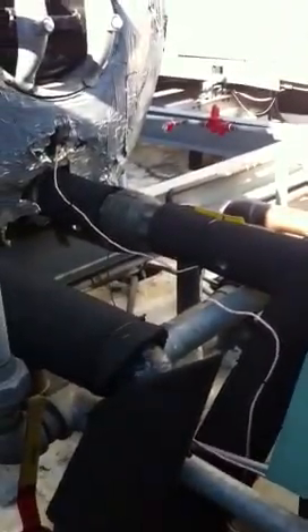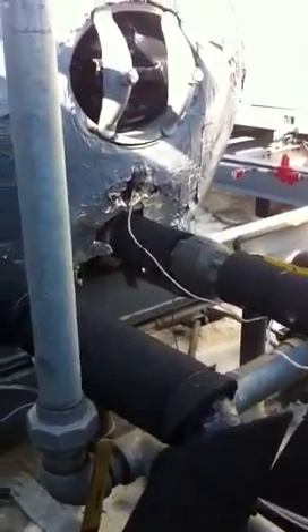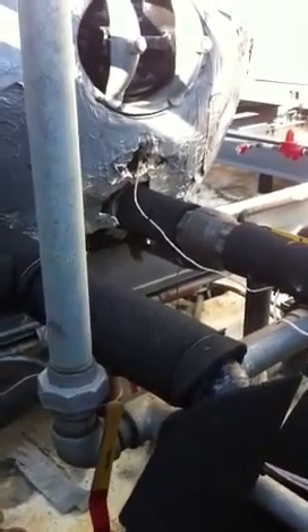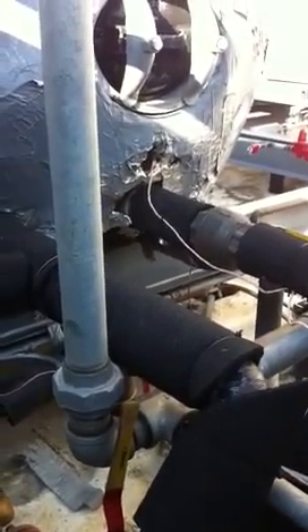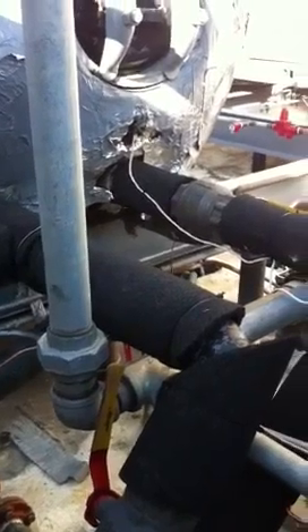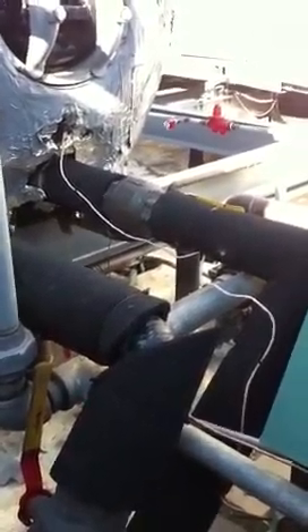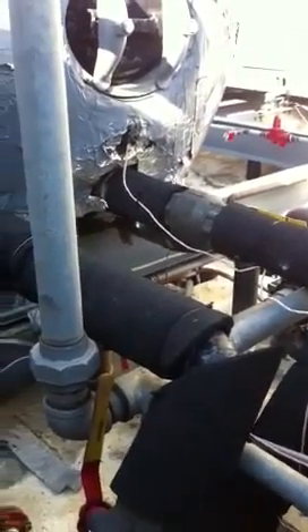It's just you're pumping through a lot more stuff that you don't have to. Plus, when the burner isn't on, the boilers act as radiators. So if you're pumping hot water through there, you're losing heat out of your hot water. So we also said that we're going to do an east boiler heat exchanger replacement. Right. This one here is going to be replaced.